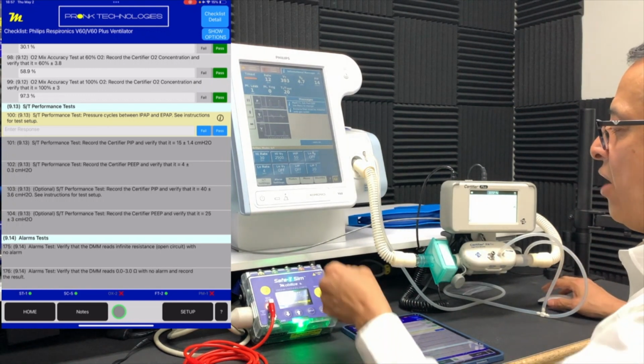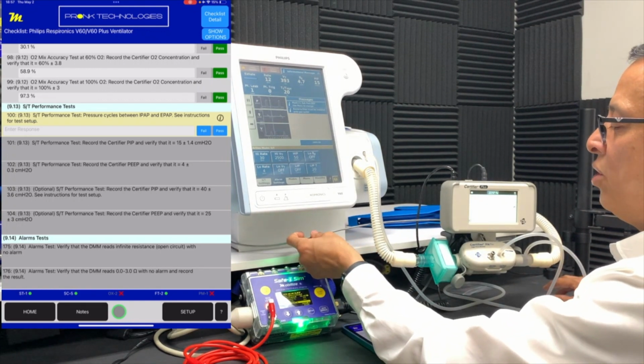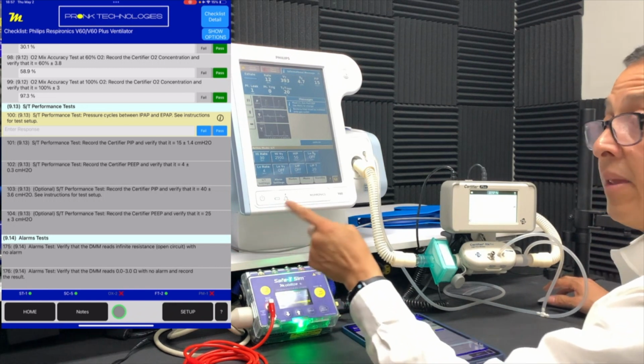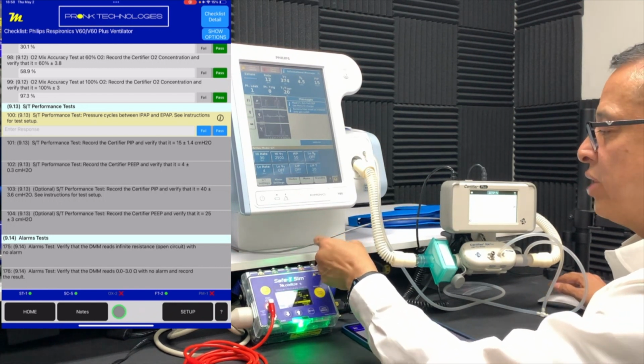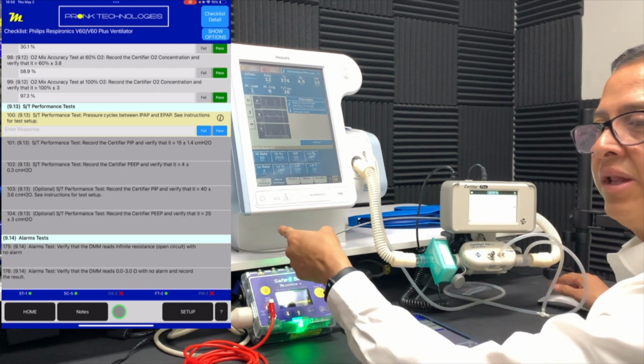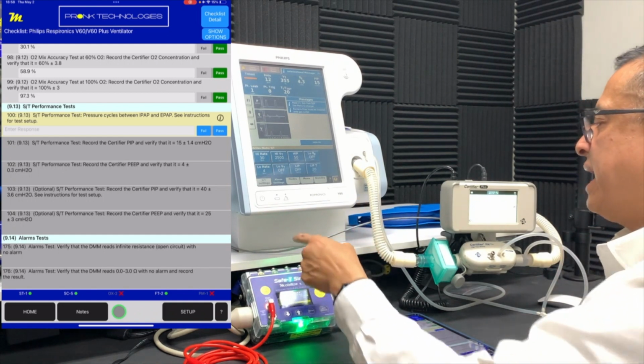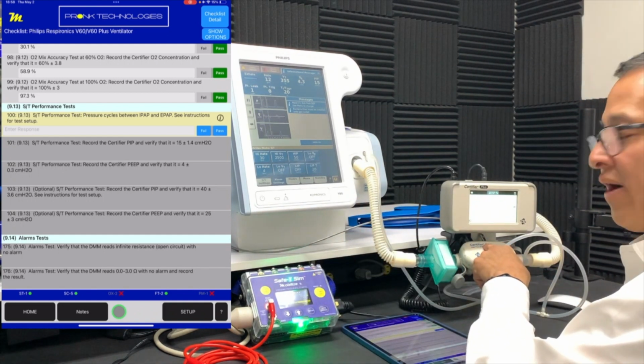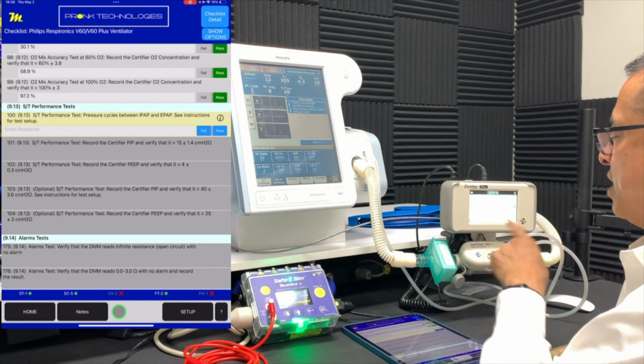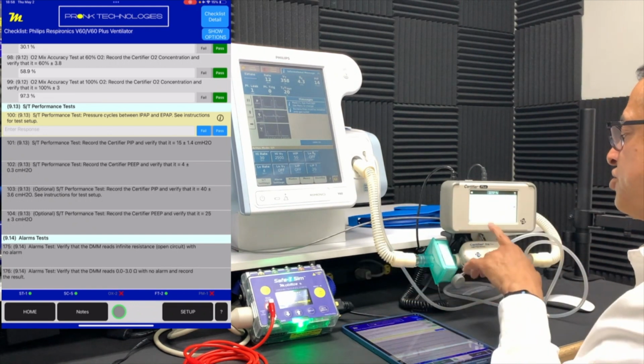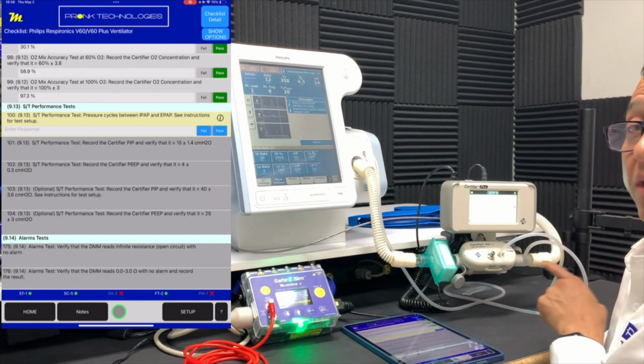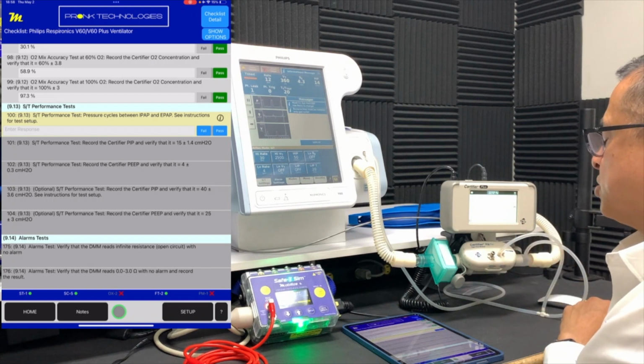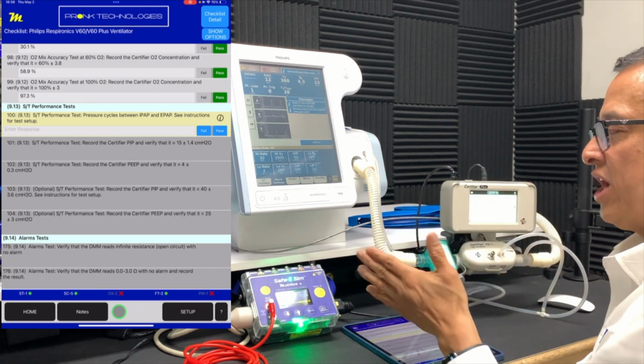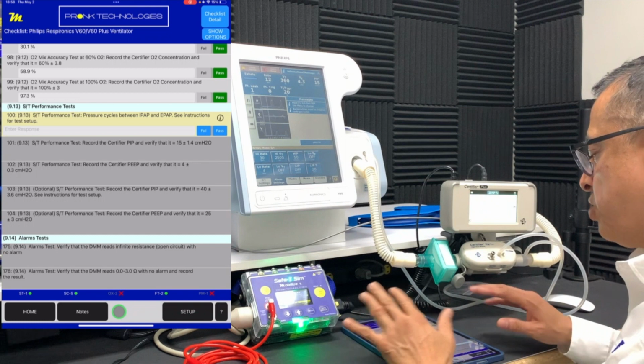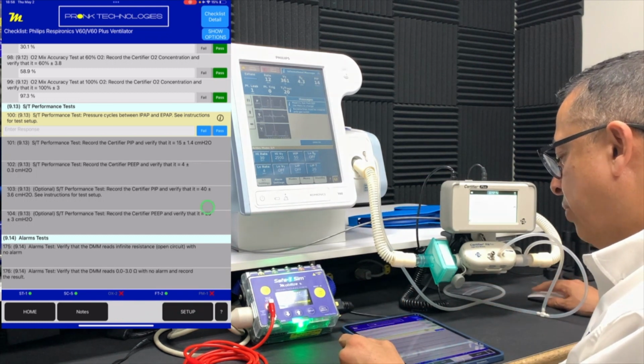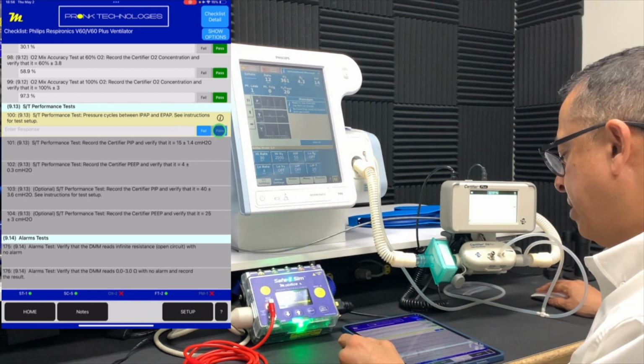You also want to now connect the trigger cable, TTL trigger cable, from the back of the ventilator. It's a special cable you have to make sure you connect from the back of the ventilator. It's got a 25-pin port there, and it connects to the certifier flow meter so that it can trigger the measurement properly. So you need to make sure you've set your analyzer to trigger at TTL high so that it can make that measurement at precisely the right timing. So you've got that configured properly. We can go ahead and finish this setup and perform the test.